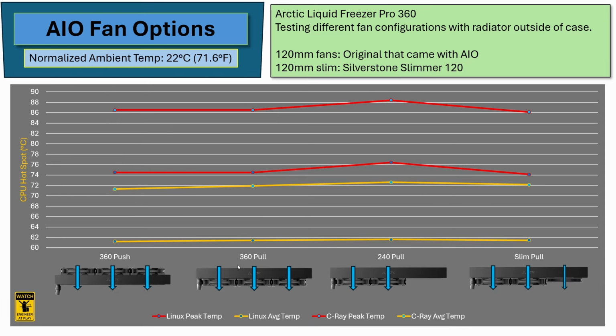Now I switch the fans over to the pull configuration. Here are the results, and I'd say on the peak side they're relatively equivalent to push, but when we look at the average it's maybe slightly elevated, not a lot, a degree at most I'd say.